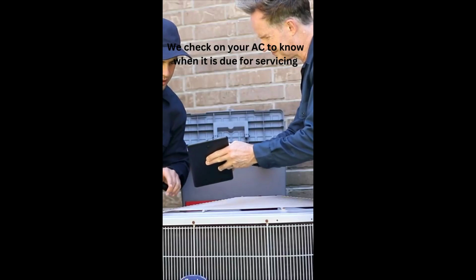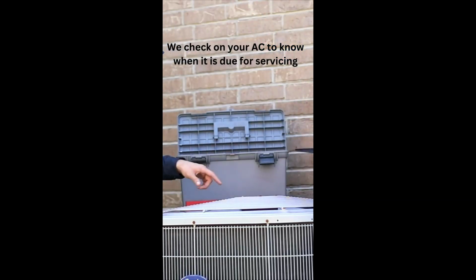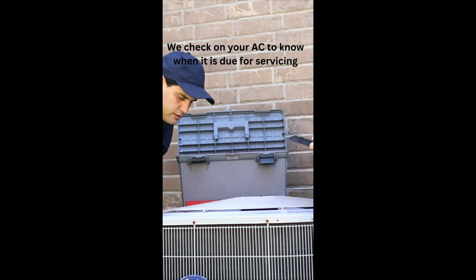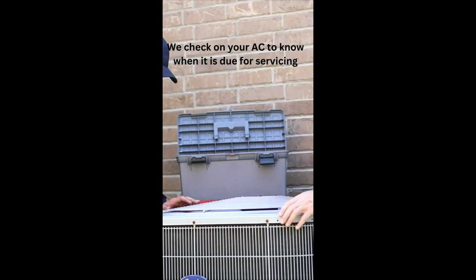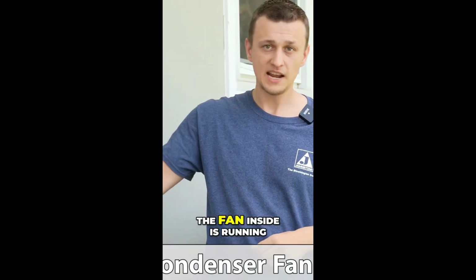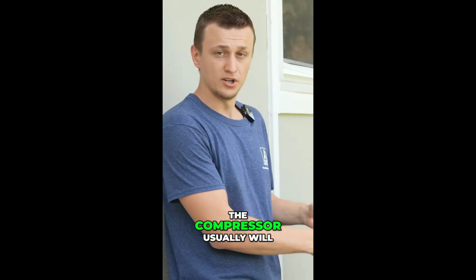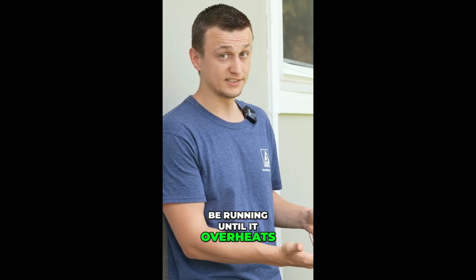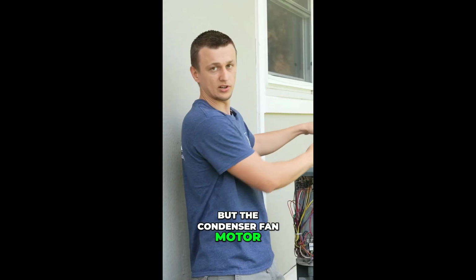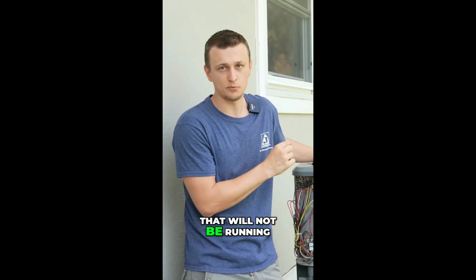We check your AC to know when it is due for servicing. We have to check the capacitor, the compressor, and the fan to see if they are all working well. This one is pretty obvious. The fan inside is running. The compressor usually will be running until it overheats. But the condenser fan motor on top of the unit will not be running.